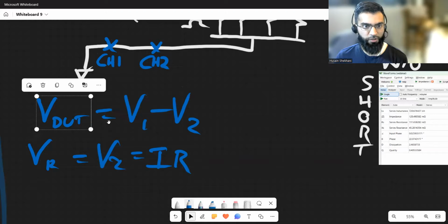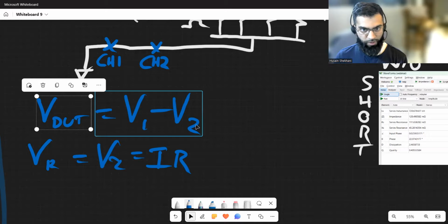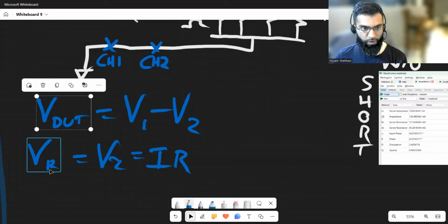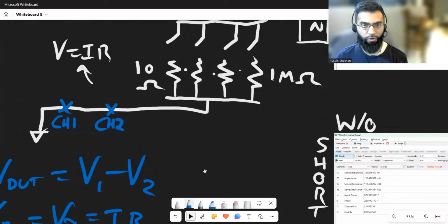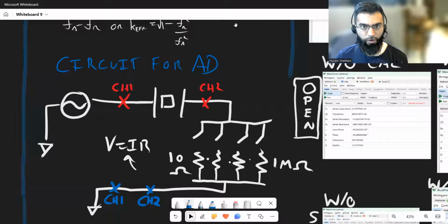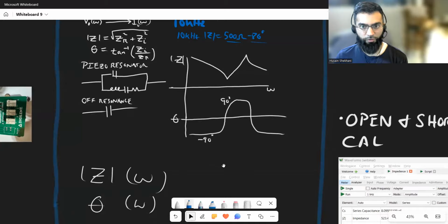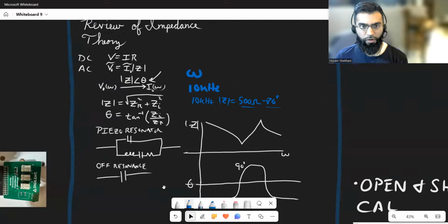The voltage across the device under test is voltage 1 minus voltage 2, and the current equals voltage 2 - that being the current times the resistance. So if you divide voltage 2 by the resistance value, you get the current, and therefore you have current and voltage, so you can calculate impedance magnitude.